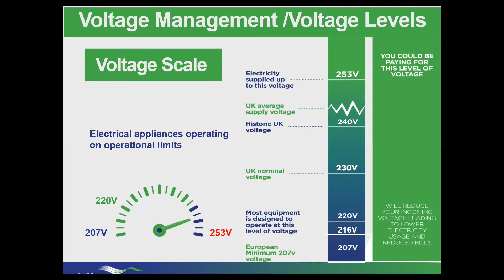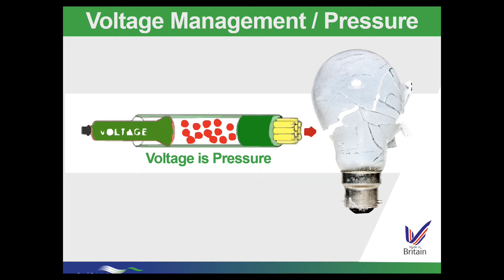A typical example of that is LED lighting. Any LED - that driver, that little transformer - if it's receiving a much higher voltage than it needs, it will deteriorate more quickly than it should. We've got lots of examples with petrol stations where the canopy lamps are failing much quicker, and a lot of industrial applications are exactly the same. So if the voltage is much higher than it needs to be, there's a lot more deterioration.